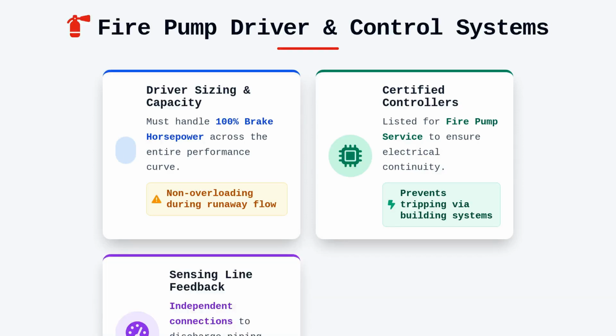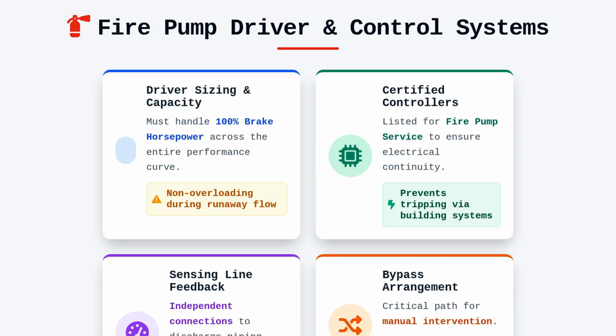We must also integrate the sensing line, which provides the critical feedback loop to the controller by monitoring discharge pressure, and it must be installed with independent connections to the discharge piping to prevent false signals. Should a failure occur, the bypass arrangement, if required by local jurisdiction, allows for manual intervention or provides an alternate path for water flow during maintenance.